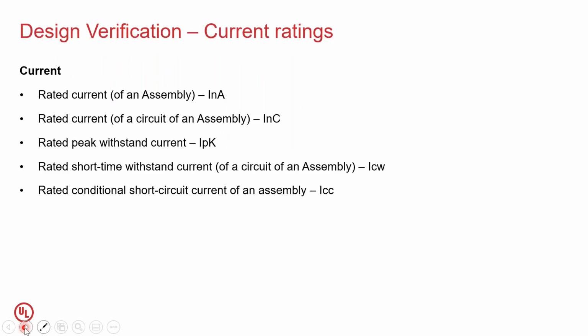Let's look at the current ratings. As you can see, there are a couple of different current ratings. The most common is the rated current of the entire assembly, which is the rated current of the busway. For example, it could be a 1000 amps busway, and that could be your InA. Now, if this busway has a plug-in unit with a 600 amps breaker, then you can declare that circuit as 600 amps. In that context, it becomes the rated current of a circuit of an assembly, also called InC.